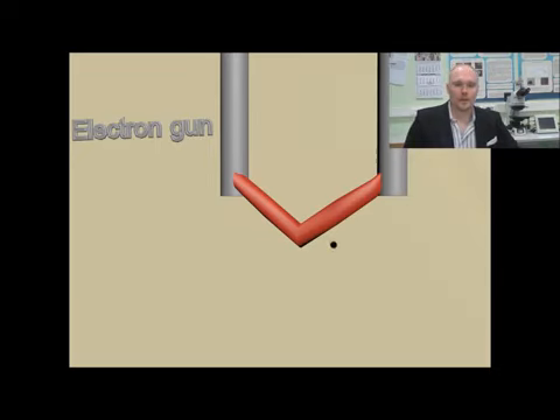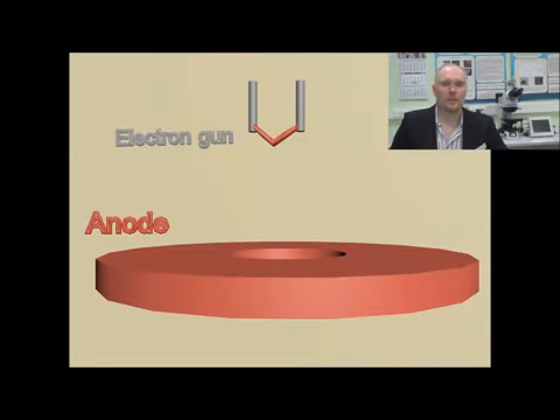There are different types of electron guns, but in the case of older electron microscopes we are usually dealing with a tungsten filament. This tungsten filament is heated up to 2400 degrees Celsius, where it starts emitting electrons. These electrons are now accelerated down the column with the help of this anode. And the accelerating potential can be from 1 to 30 kilovolts, which is selected by the microscope operator.